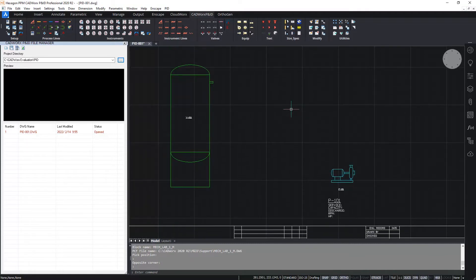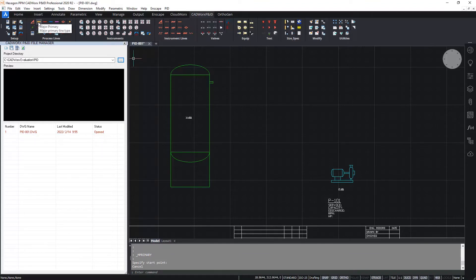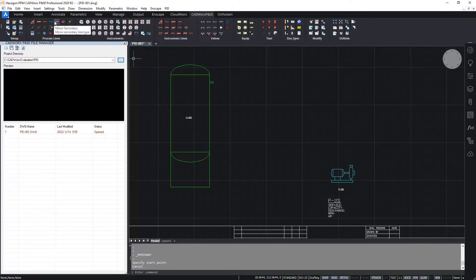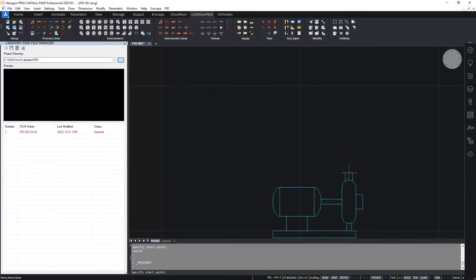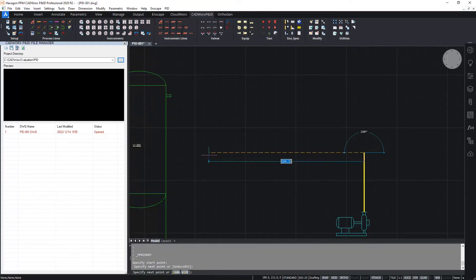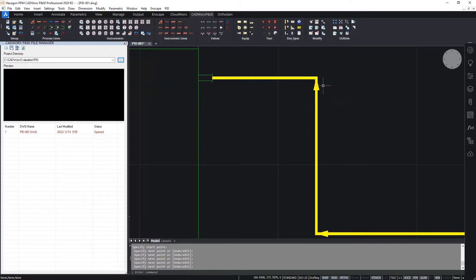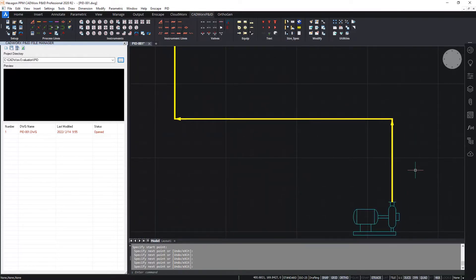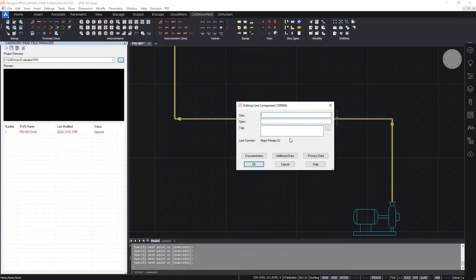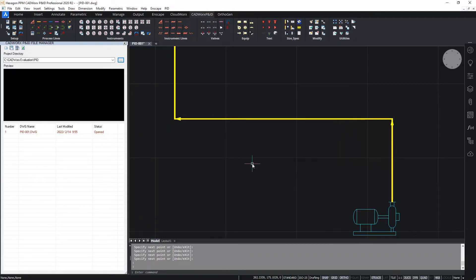Next in this simple P&ID, I'll draw a process line connecting from the pump to the vessel, from the pump discharge nozzle to the vessel. There are various different available lines within CADWorx, all completely configurable. The most commonly used lines are these ones on the icons here: the major primary and secondary, and the minor primary and secondary. I'll choose a major primary process line. I'll start from the pump discharge nozzle and go across and connect up to the nozzle on the vessel. Once I hit enter to finish, as you can see, the flow arrows are placed automatically at each vertex of the line. If I double click on the process line, I could then add a tag.